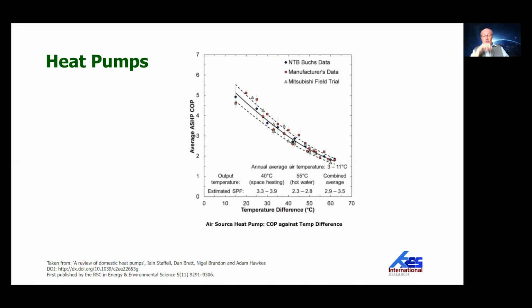Now, the coefficient of performance depends very much on the difference between the input temperature and the output temperature. So, for example, if you have a 20-degree difference, so you want to get to 20 degrees output temperature and the input temperature is 0, then your coefficient of performance can be quite high. But if the temperature difference is, say, 60, so the input temperature is 0, it's an air source heat pump, the temperature of the air outside is 0, it's freezing, and you need 60 degrees for your heating system, then the coefficient of performance is likely to be much smaller, kind of 2 or 3 or something like that.